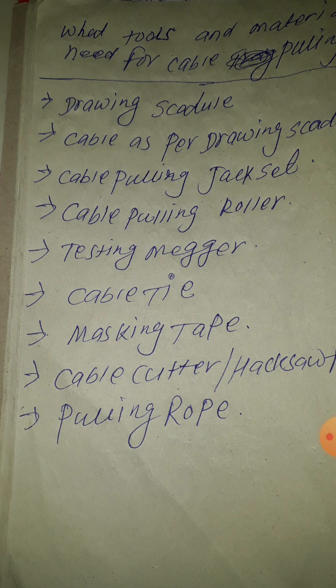And if you are pulling at ground level you should use rollers, because if you do not use rollers and pull directly, your cable insulation is damaged, and then the cable is damaged, which is a problem for you. Especially at ground level pulling time, you should use rollers. Inside a duct we do not need them, only a rope to pull. So at the corner of the cable tray and at ground level pulling time, you should use cable rollers for insulation protection.